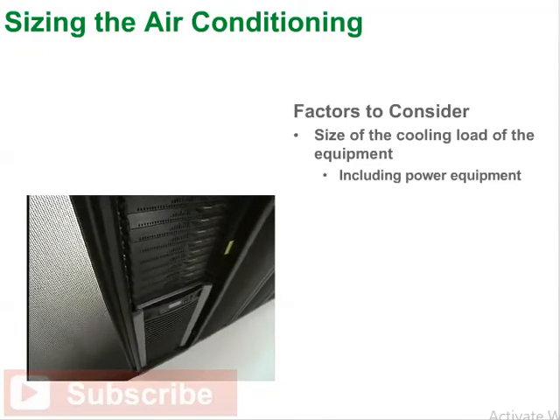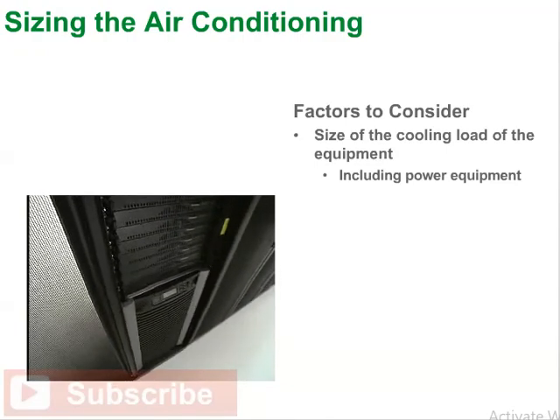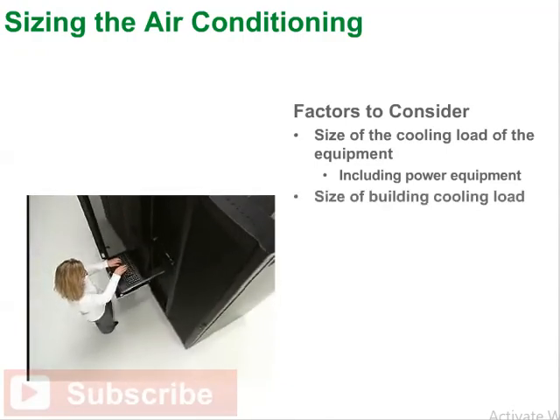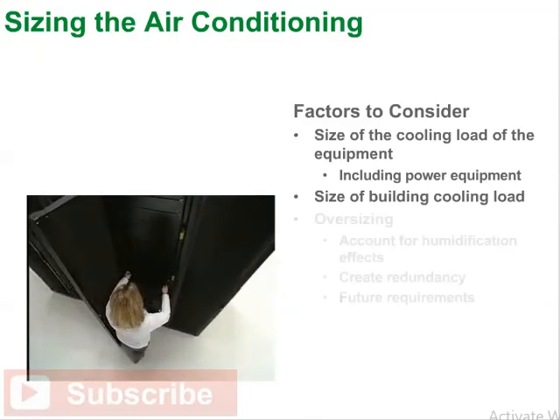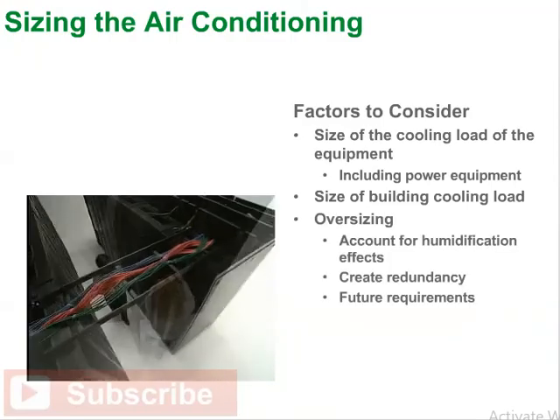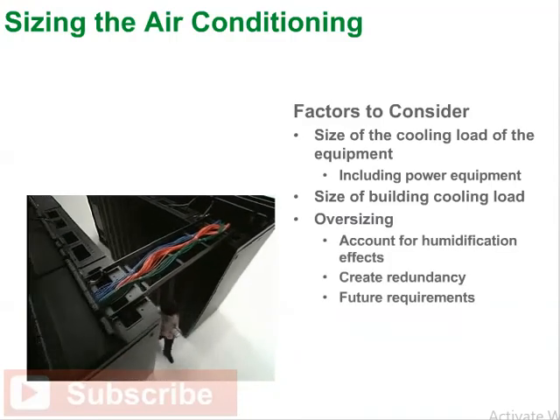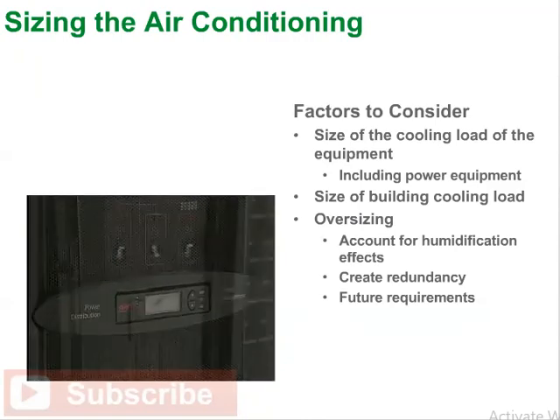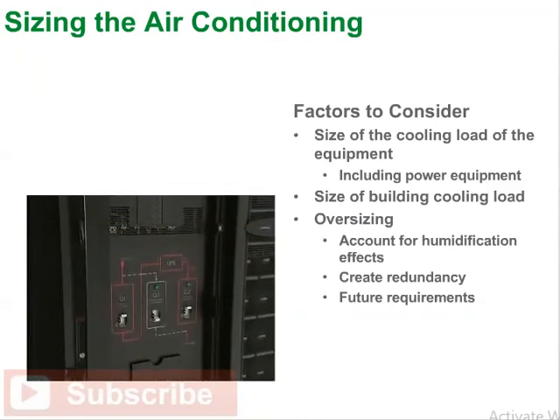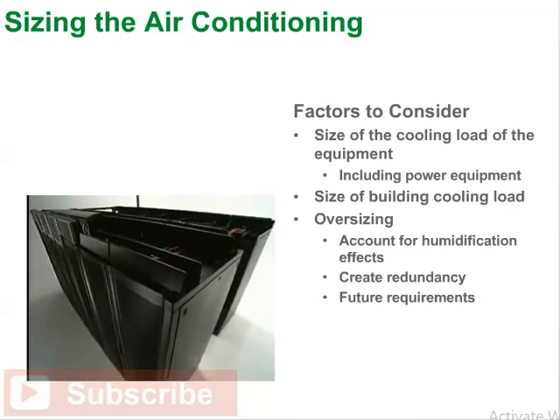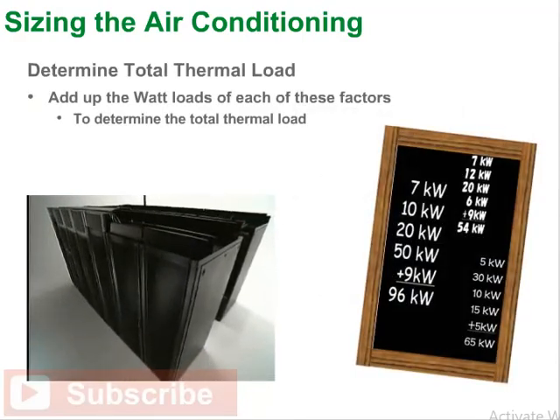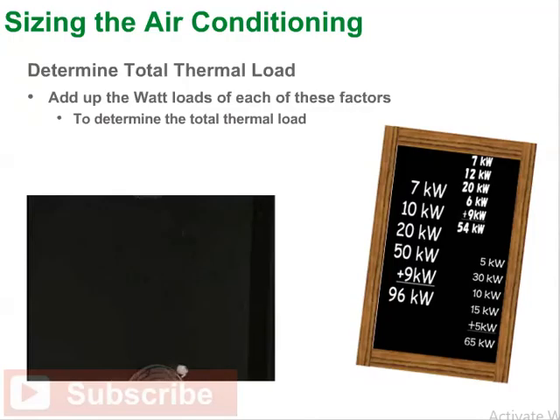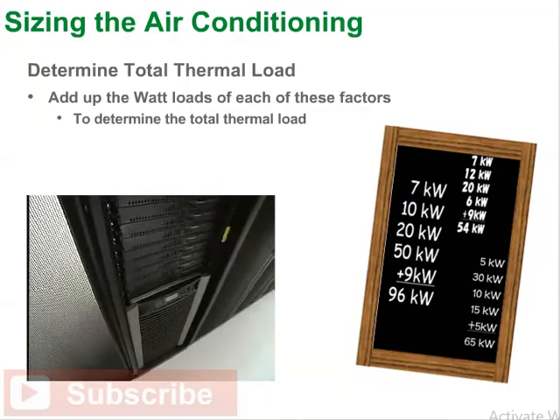The following factors must be considered when sizing an air conditioning system: the size of the cooling load of the equipment including power equipment, the size of the cooling load of the building, oversizing to account for humidification effects, oversizing to create redundancy, and oversizing for future requirements. The watt load of each of these factors can be summed to determine the total thermal load.